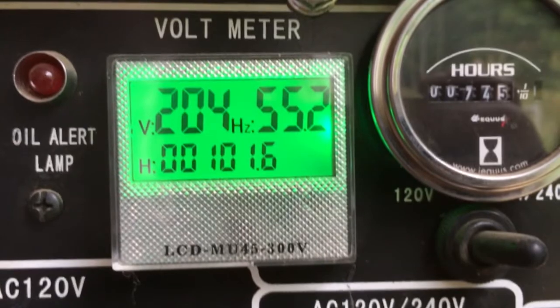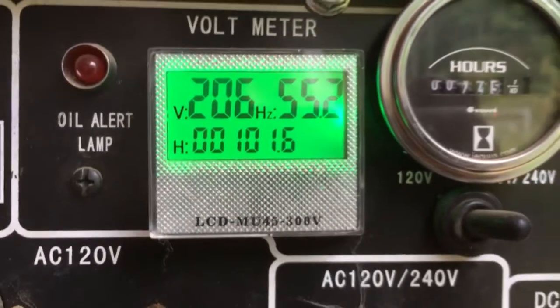It is not staying on frequency. The voltage runs low when it runs slow and the voltage runs high when it runs fast. Most of all, it will not hold steady speed. Steady speed is manifest as cycles per second, or your line frequency. If your line frequency is off, some appliances really hate that — my lights flicker, things aren't working right. If you look at the meter, you'll see the voltage and frequency are wrong.